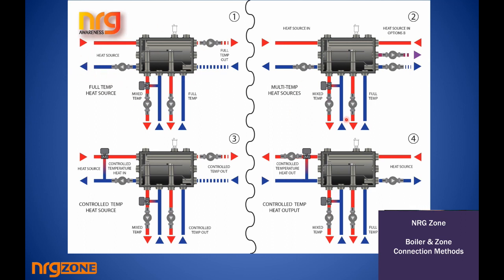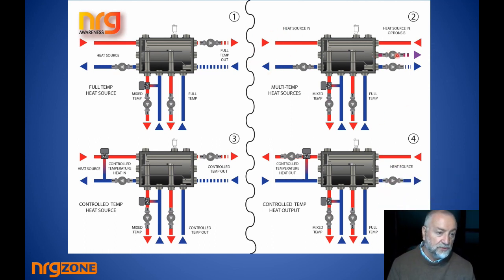The one on the right is where you might decide to have multiple heat sources. You might have, say, a heat pump or a condensing boiler, say for instance over here, and then you might, if you want to use the middle return connection, you might have solid fuel or a pellet boiler. The flows would return into here. This is just a different way to do it to what I showed last time.